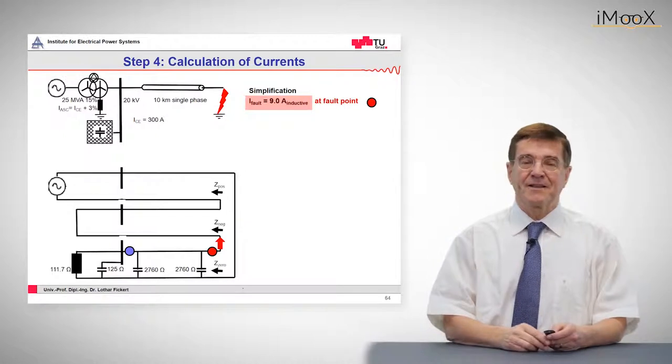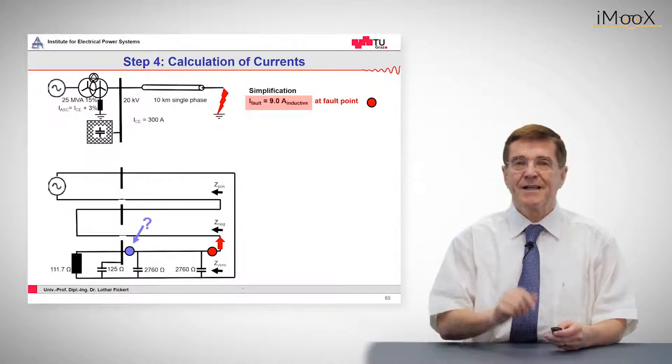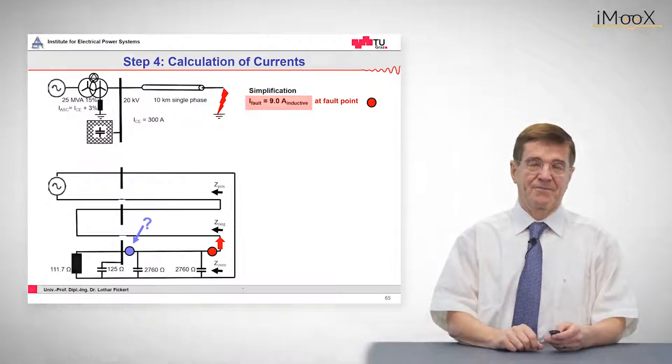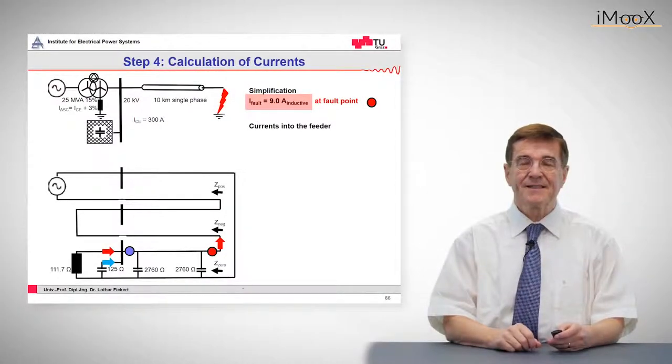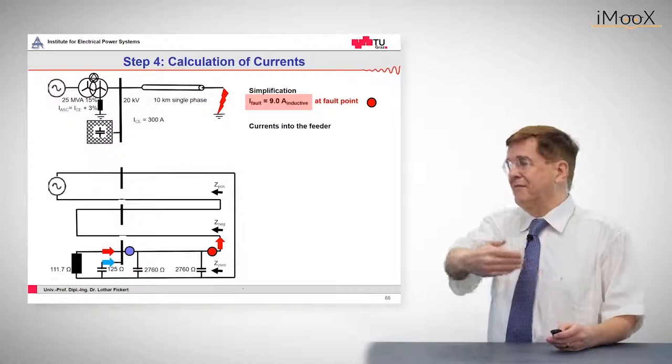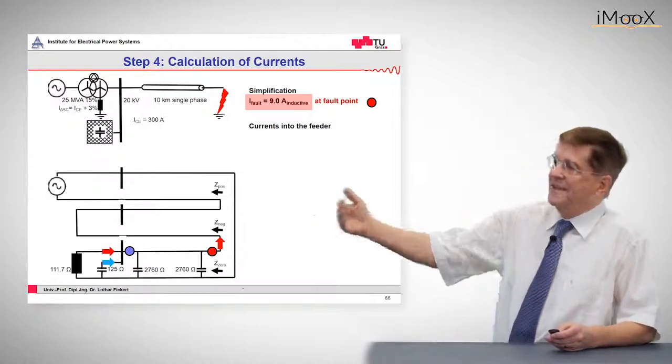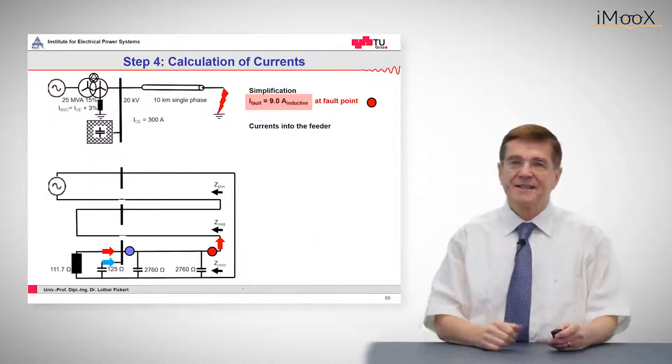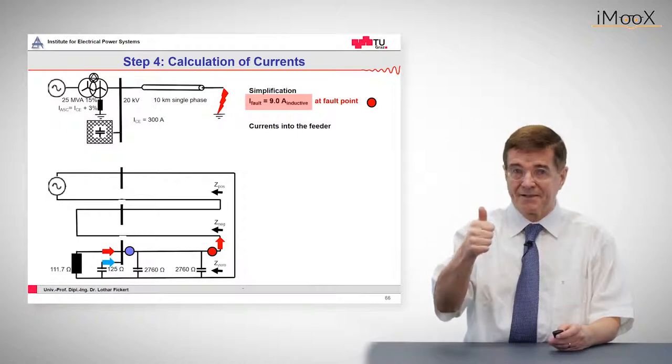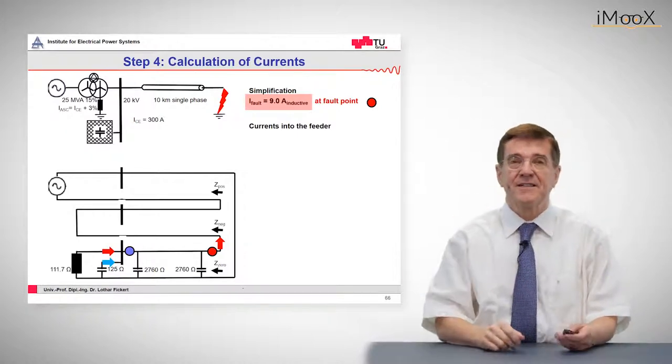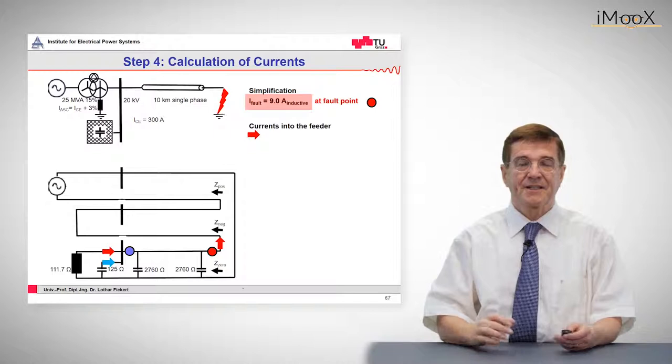Now let's see what happens at the fault point. That was the 9 amps. And now what is the relay given? So the relay sees the currents that are fed from the left side into the feeder. That is on one side the inductive current, on the other side it's the residual capacitive current. And they are calculated here.